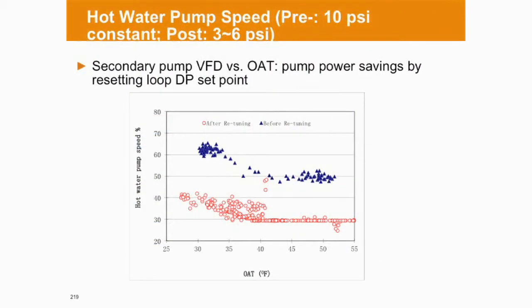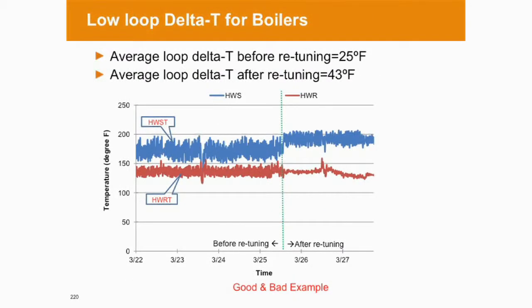And then this basically shows the savings from doing that. The pre was around 10 psi, a constant set point. The post was about a 3 to 6 psi set point that automatically adjusts. And then your pump speed, the blue triangles show you where you're running about 50 to 60, almost 70%. And it increases as it gets colder outside, which makes sense. And it drops significantly. So again, based on what Gupong shared earlier with the affinity laws, there's probably some substantial savings. We don't know the size of this pump or pumps. This is a little bit different. This is a fabricated chart.